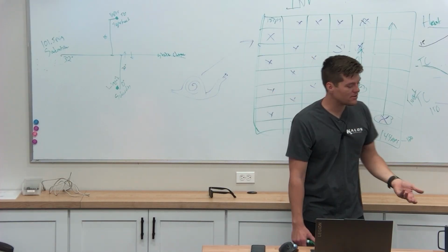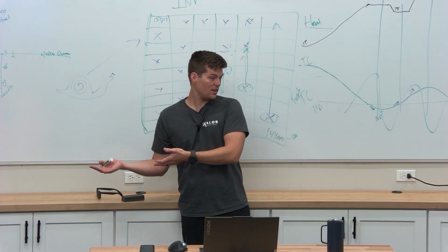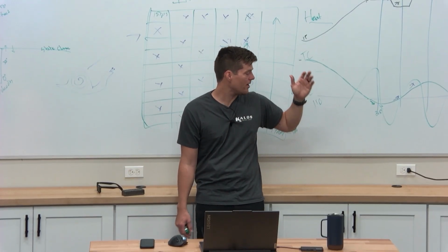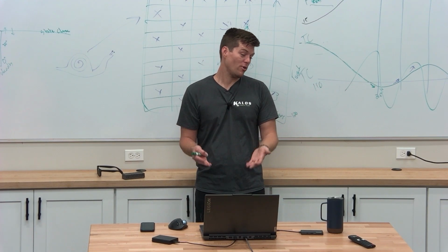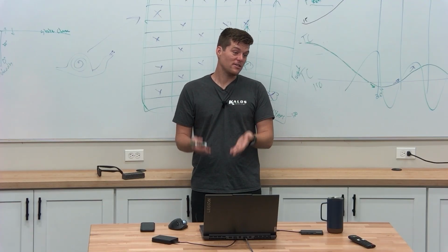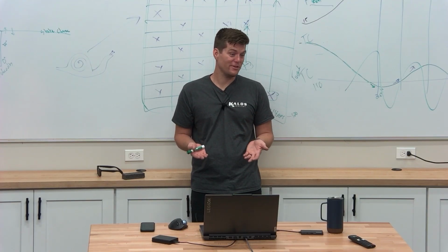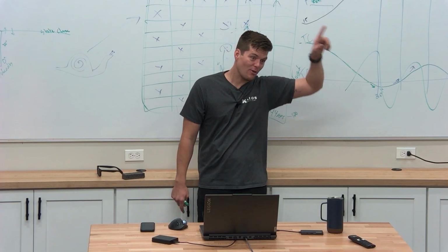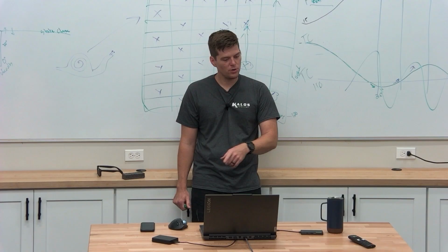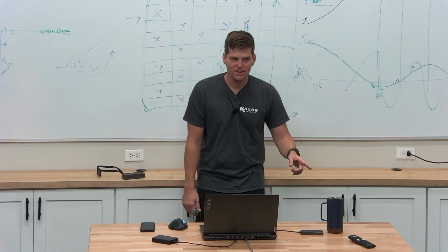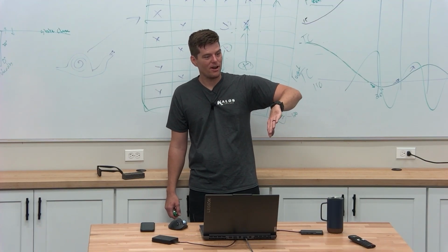So you have to decide in the system, is it connected to my suction line? Is it a vapor? Or is it a liquid? And you're going to find in certain parts of the system where it doesn't make any sense. And you look at it and you're like, well, this is my liquid line, but it's 4 degrees. That's a lot of subcooling. But then you have to ask the question, okay, what if it was a vapor? Let me follow it all the way back where it came from. Okay, was it supposed to turn to a liquid at some point? What if it never turned to a liquid? Or what if it barely turned to a liquid and then turned immediately back into a vapor? What would that look like?